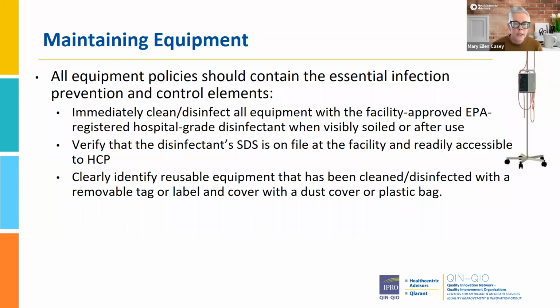Immediately cleaning and disinfecting the equipment with a facility-approved EPA disinfectant is very important when visibly soiled or right after use. Another thing is to verify that the disinfectant's safety data sheet is on file at the facility and readily accessible. If you've never seen one, safety data sheets are required for a facility to have on hand, whether online, which updates automatically, or a paper copy, where you're responsible for keeping it up to date. It tells you the ingredients of the disinfectant, how to use it, the PPE to wear, and what to do in the event of an exposure.